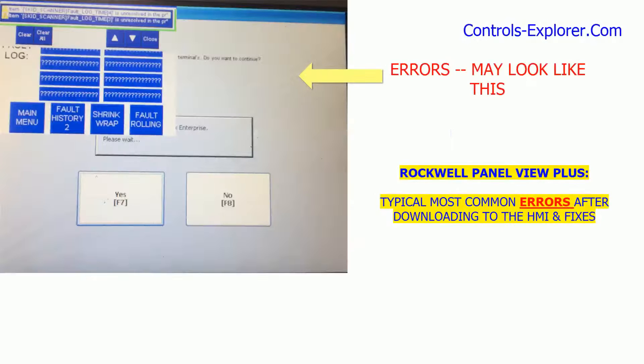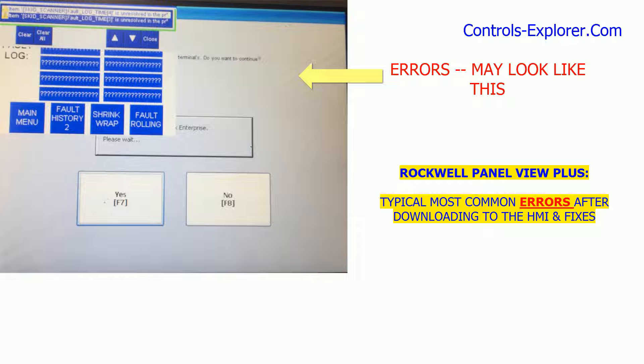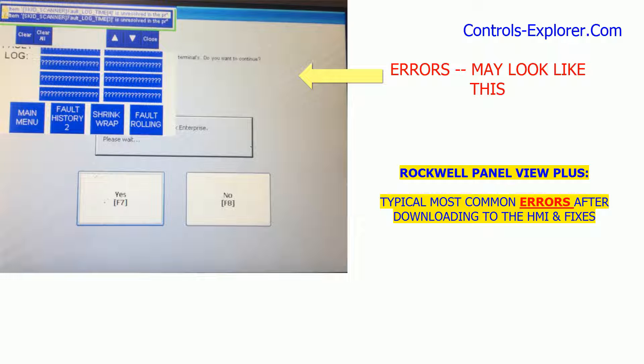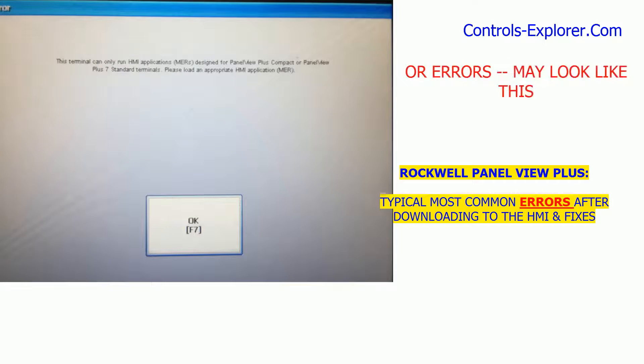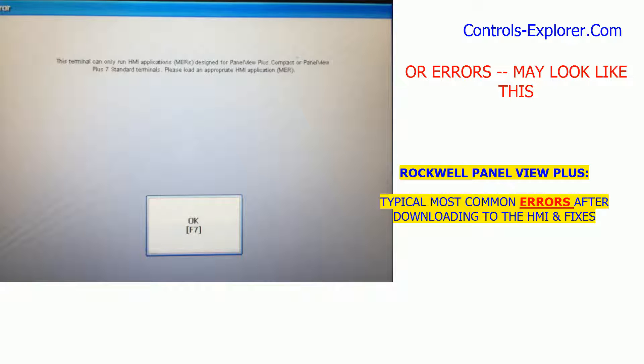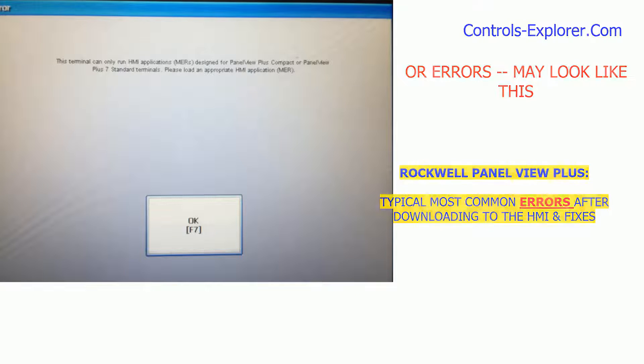One of the errors, as you can see, instead of occupying the whole screen, the image is right at the corner of the HMI. Or there could be other kinds of HMI errors as well, for example this one which says please load an appropriate HMI application for this HMI, which basically tells you nothing except for the fact that there is an error.